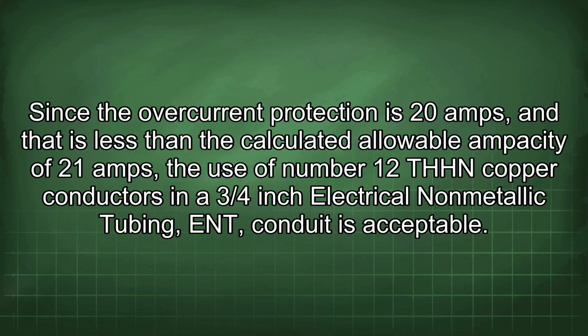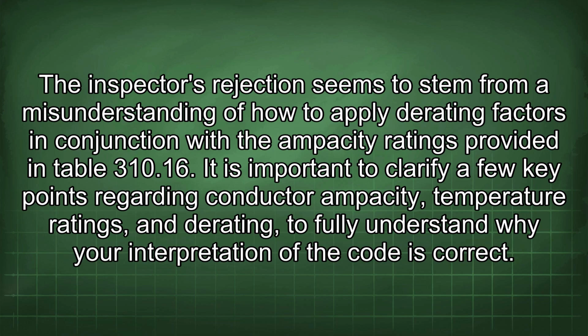Since the overcurrent protection is 20 amps, and that is less than the calculated allowable ampacity of 21 amps, the use of number 12 THHN copper conductors in a 3/4-inch electrical non-metallic tubing, ENT, conduit is acceptable. The inspector's rejection seems to stem from a misunderstanding of how to apply derating factors in conjunction with the ampacity ratings provided in Table 310.16.